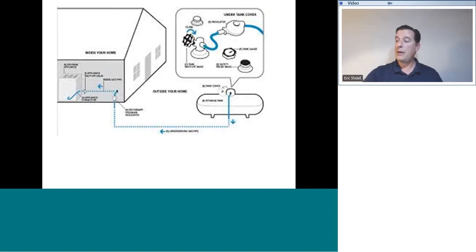So there's a primary regulator right on the top of the tank, right underneath that little dome. And that primary regulator is going to step the pressure down from whatever that super high pressure in the tank is to a much more reasonable level, somewhere in the 14 to 28 inches of water column range. If there is a very long run and a very small pipe, that pressure controlled by that regulator may need to be higher.